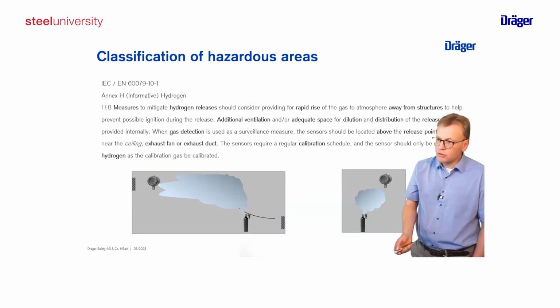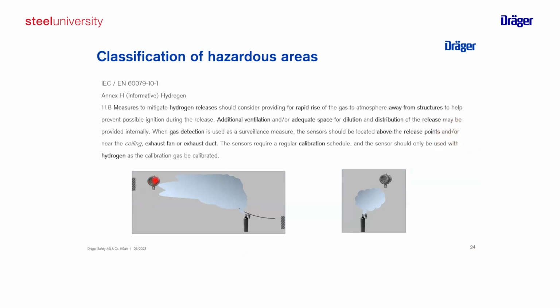When you position detectors, you also need to consider that they need maintenance. You need from time to time to check and calibrate them. So the positioning should also consider the work of your maintenance people. There are possibilities, for example, we offer a remote calibration adapter so that you still have a point detector under the roof, but by using accessories, you can apply the test gas concentration or calibrate the sensor from the ground. But this needs to be considered during your design phase.